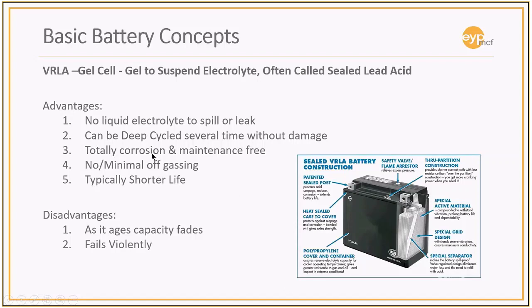But they're supposed to be totally corrosion and maintenance free. Nothing ever is really totally maintenance free. No off-gassing, though there is some hydrogen that can be produced. In the flooded cells, there is definitely hydrogen produced during charging. We have issues with authorities having jurisdiction not necessarily understanding the difference between a flooded cell and a valve-regulated cell, and requiring hydrogen detection and hydrogen exhaust in a valve-regulated environment.